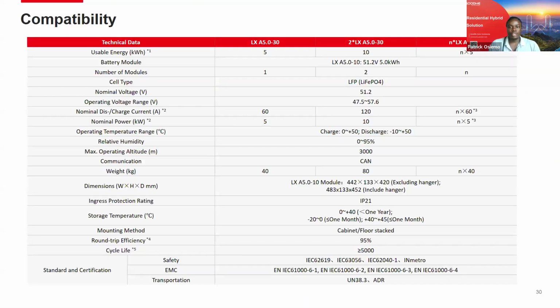Now I'll start with the Gen 3, and these are the specs. The battery itself is 1.5C, so a 5 kilowatt hour battery can support up to 7.2 kilowatt in terms of charging. The same battery can also support a constant 5 kilowatt load. When you scale up, it's just a matter of adding up the power capability of the batteries. It's an indoor battery, able to charge and discharge at high currents, operating at low temperatures, depending on whether it's charging or discharging, and up to 50 degrees when charging or discharging.